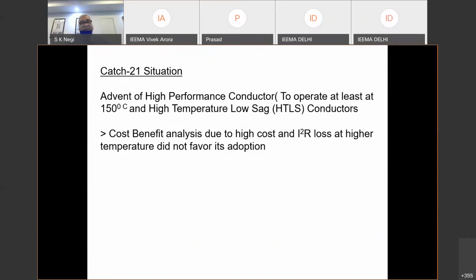So we were in a catch-22 situation, because as I said, after 2000, ROW issues came into the picture, and we had all the lines with the traditional ACSR Moose conductor, and we were having issues laying other lines. That is how the high performance conductor and HTLS conductor attracted people, and they started telling us, please use this conductor. But cost prohibited utilities from using that. Nevertheless, for a short line, this HTLS conductor is definitely very, very useful, and it was required.